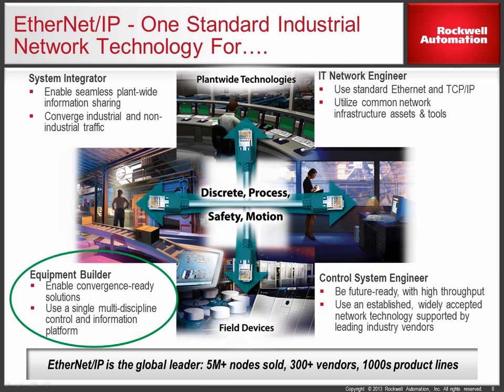Because EtherNet/IP is standard, multiple application layer protocols can coexist on the same common network infrastructure — for example, CIP (the Common Industrial Protocol), Modbus TCP, IEC 61850, web applications with HTTP, and video and voice with Real-Time Transport Protocol. However, coexistence does not mean interoperability. Rockwell Automation has multiple Encompass product reference partners that provide gateways to translate between CIP and other protocols or EtherNet/IP and other networks.